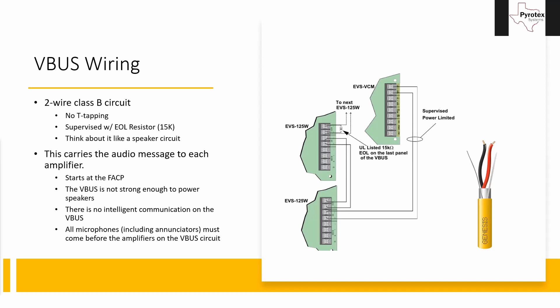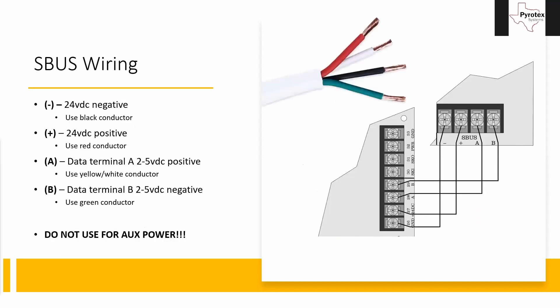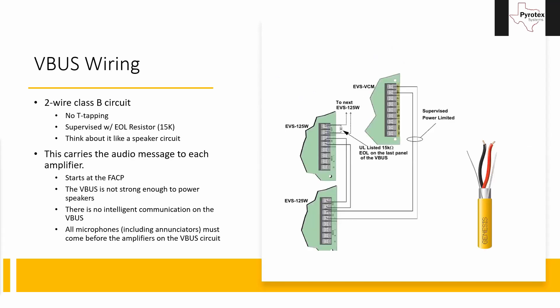On each of these slides I've also shown the type of wire needed. For VBUS, you use yellow-jacketed shielded two-conductor wire — the same wire used for speaker circuits. For SBUS, it's the white-jacketed four-conductor wire. Sometimes wire colors may need to be red or red-with-yellow-stripe if an engineer specifies a particular color, but whenever we have the choice, these are the preferred colors to keep everything straight in our panels.